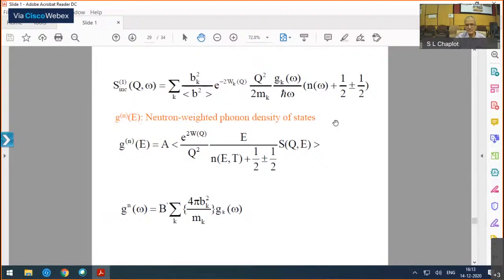One of the ways we do this is by calibration. We may use a standard sample. Often it's a vanadium sample. And the good part about vanadium is that its coherent scattering cross-section is negligible. Because it has essentially only the incoherent scattering cross-section, there are no complications because of the structure or the collective dynamics. And therefore, the dependence on the wave vector is very simple.